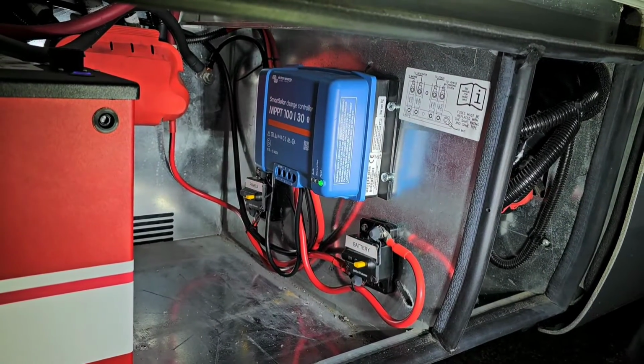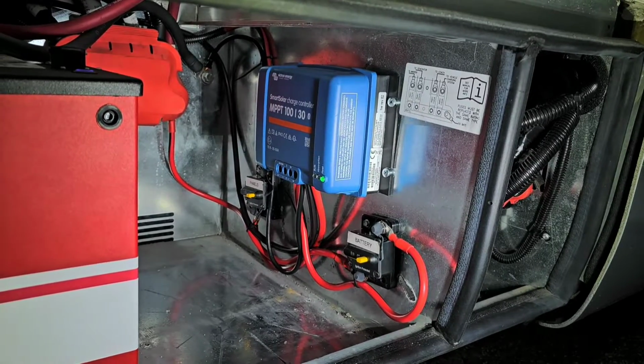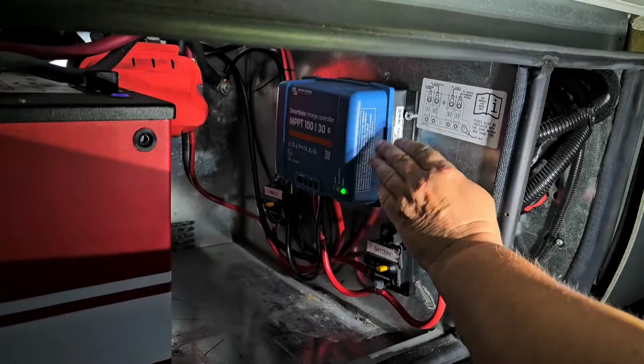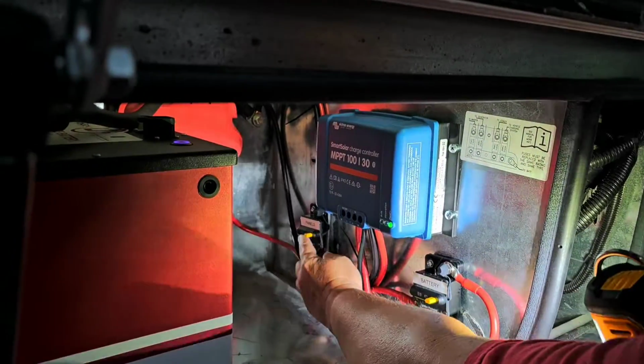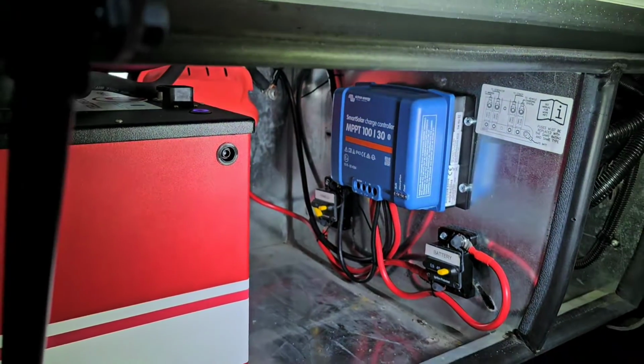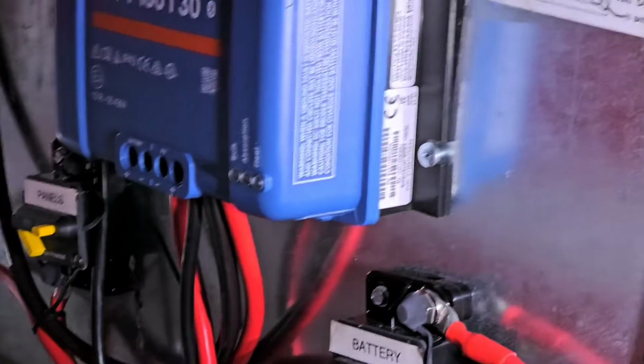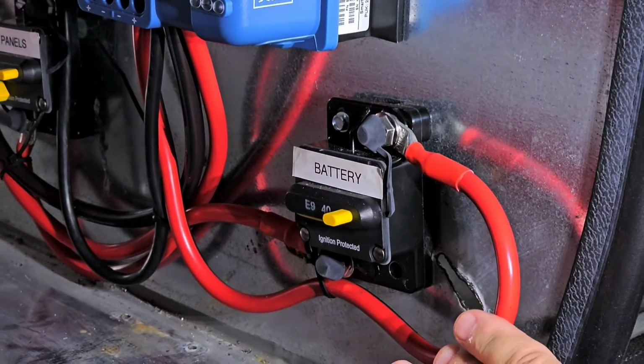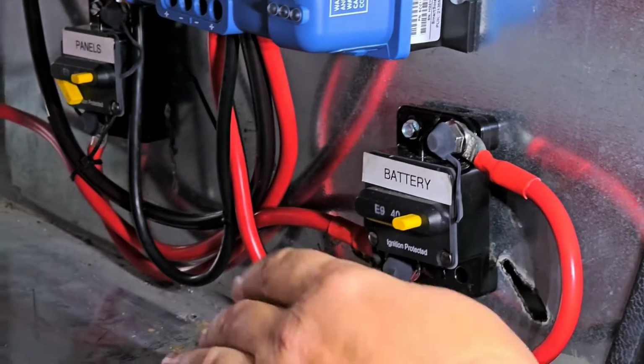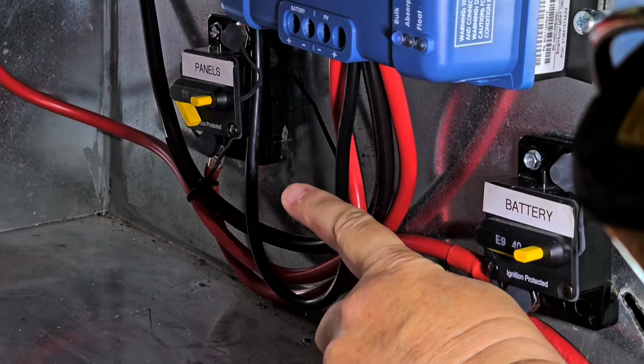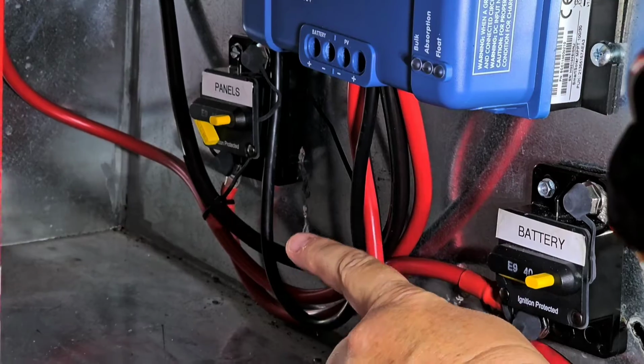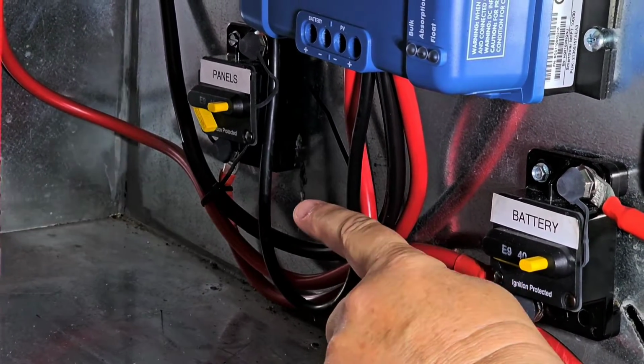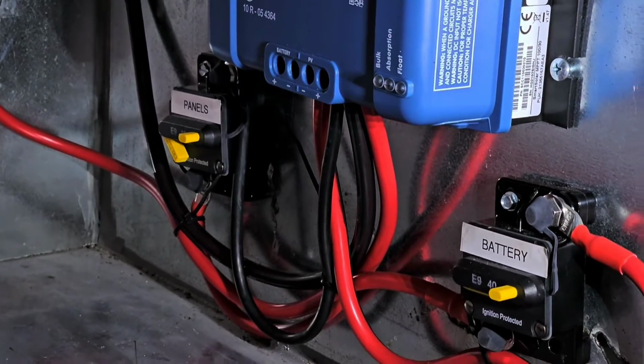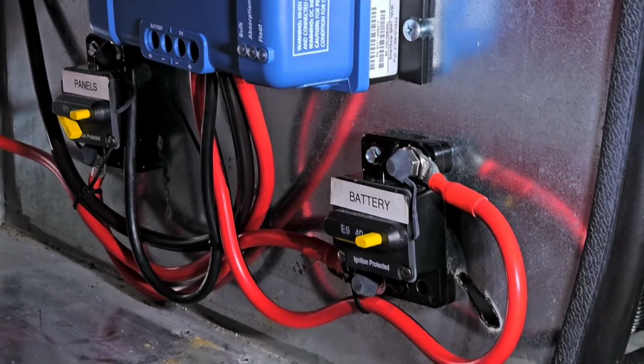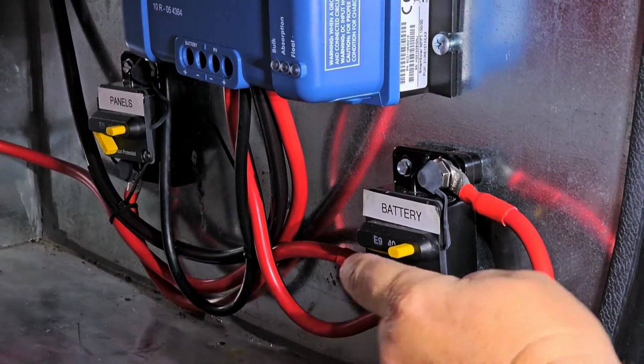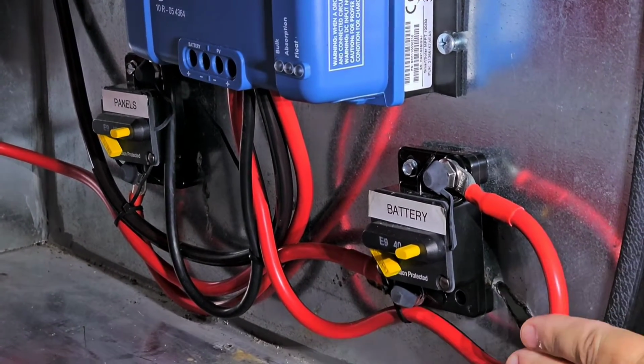Now we want to shut down the power for the solar. The first thing you always do when cutting off your solar, so you don't damage your solar controller, is trip your solar panel power circuit breaker first. In this case, we installed a circuit breaker instead of a switch going to the battery. We used a circuit breaker for the solar panel power instead of just a switch, and I like using circuit breakers because you can also use them as a switch. Then we have a circuit breaker going from the solar controller to the battery. So you always want to turn your solar panel power off first, then trip your circuit breaker for the battery, and that kills all the power.